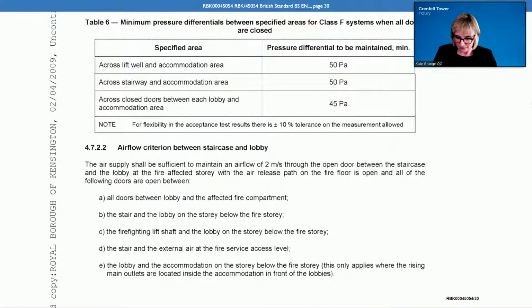He says the control system will also have pressure sensors added into each ventilation lobby to control the speed of the fans, to ensure that when the doors on the escape routes are closed, the opening force on the door does not exceed 100 newtons as detailed in BS EN 12101 Part 6. This was witnessed by your Mr. Alan White, and the reading, which was not recorded in our commissioning sheets, but read as 85 newtons on the scale provided by JS Wright.